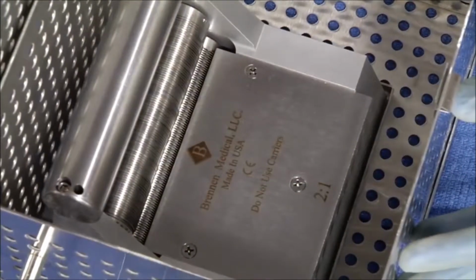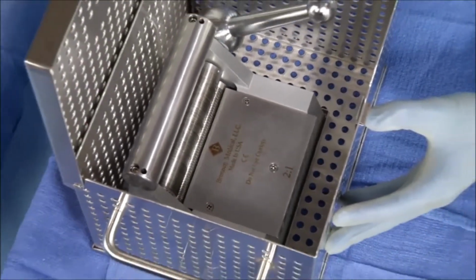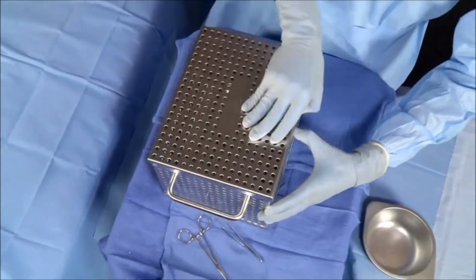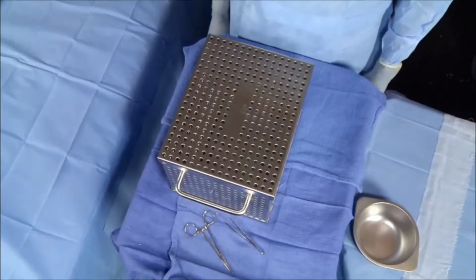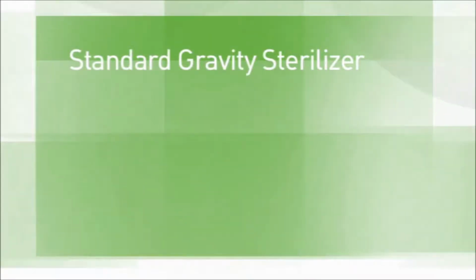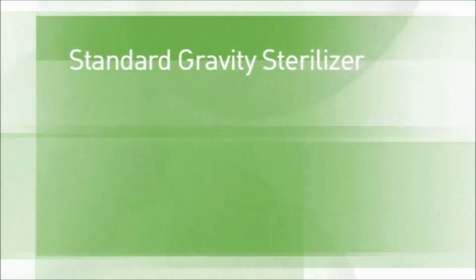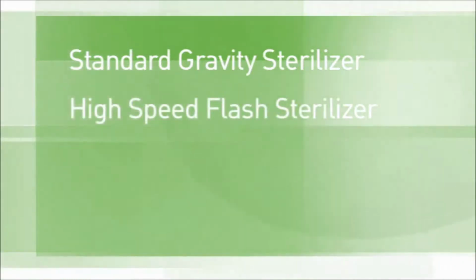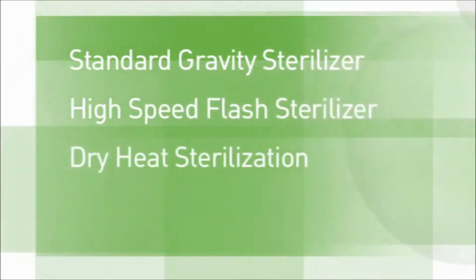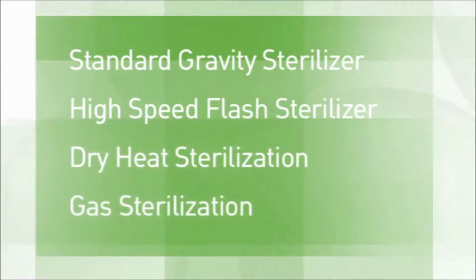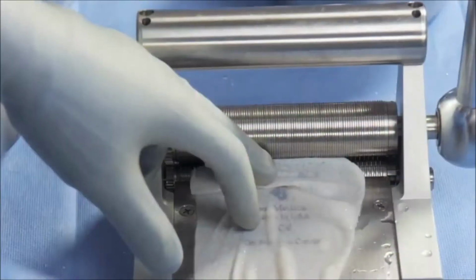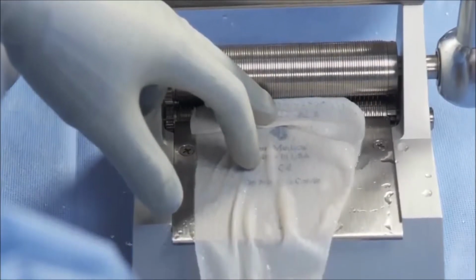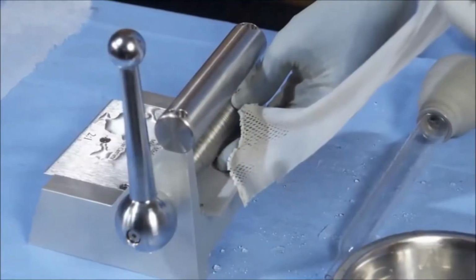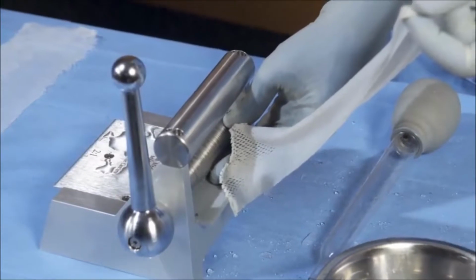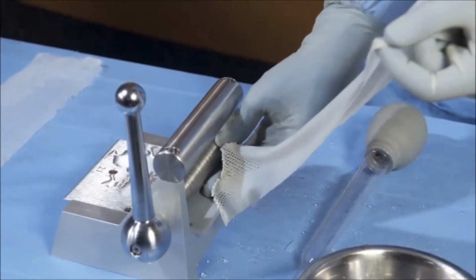After the mesher is wiped clean, it should be placed back into its carrying box, and it will then be ready for sterilization. The Brennen Skin Graft Mesher may be autoclaved using a standard gravity sterilizer or a high-speed flash sterilizer. Dry heat sterilization or gas sterilization can be substituted according to your normal sterilization procedure. Do not attempt to use the mesher until it is thoroughly cooled. The instrument may be cooled more rapidly by immersion in room temperature or cool sterile water.